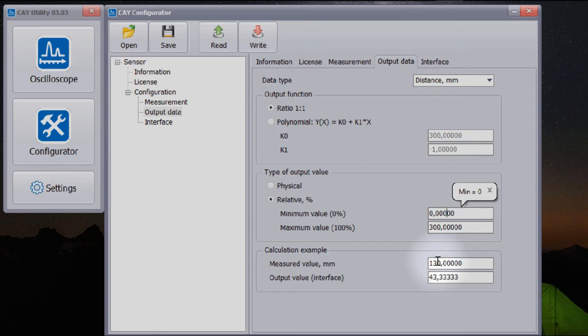If 1 mm resolution is not enough, you can set a scale factor of 10 to the sensor results. So, with a measured 100.5 mm level, the sensor will provide a value of 1005, which you can recalculate to values with a decimal point at the software side. And you can decrease the sensor resolution as well using a scale coefficient of 0.1 on its output.